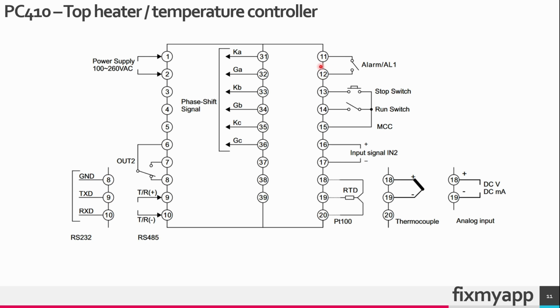Terminals 11 and 12 can be used to drive an output for an alarm. You can connect an LED or a buzzer. On terminals 13 and 15 you can connect a toggle switch, and when you press this toggle switch it will stop the program. Between terminals 14 and 15 you can connect a switch, and when you press this switch the program will start, so it will run the program. And last, on terminals 18 and 19 you can connect the thermocouple.